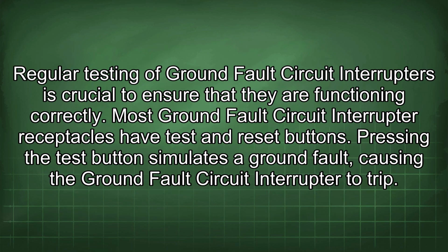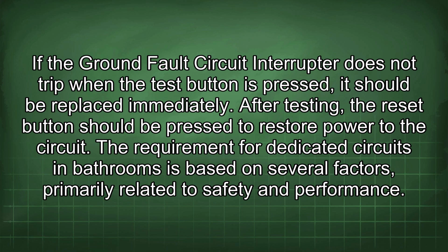Regular testing of ground fault circuit interrupters is crucial to ensure that they are functioning correctly. Most ground fault circuit interrupter receptacles have test and reset buttons. Pressing the test button simulates a ground fault, causing the ground fault circuit interrupter to trip. If the ground fault circuit interrupter does not trip when the test button is pressed, it should be replaced immediately. After testing, the reset button should be pressed to restore power to the circuit.